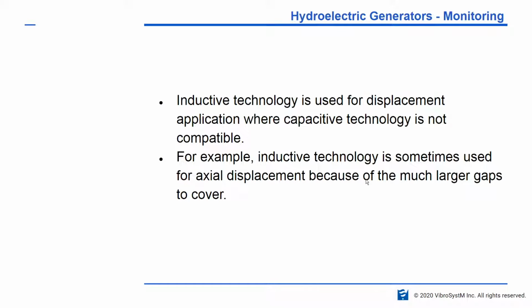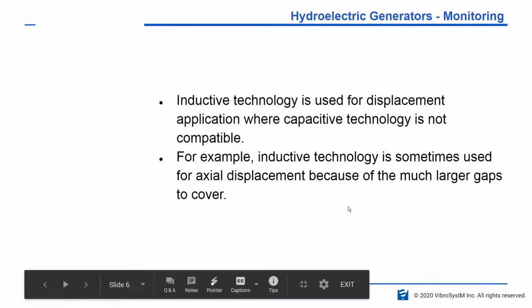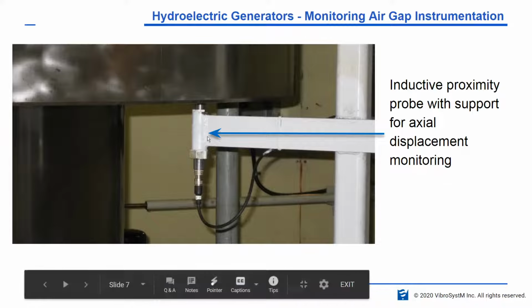Now, inductive technology is used for displacement applications as well, mostly where capacitive technology is not compatible. For example, inductive technology is sometimes used for axial displacement because of the much larger gaps to cover. It's difficult for a capacitive probe to go 15, 20 millimeters, where an inductive probe can provide significant precision for you to do that. So I have an example here. We have a sensor here, and it's looking at the axial movement of this unit.